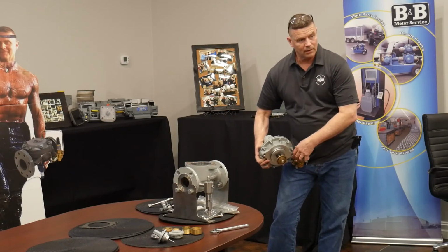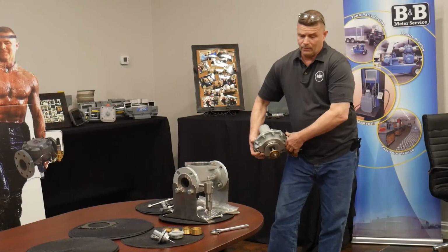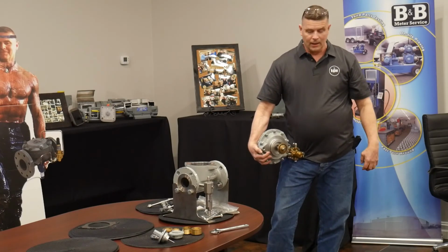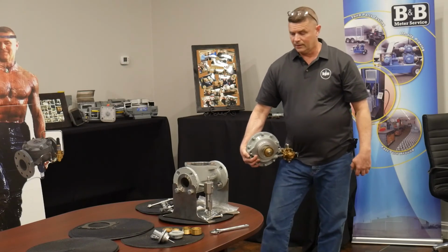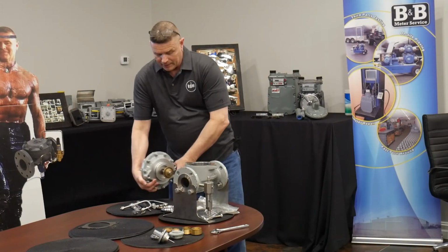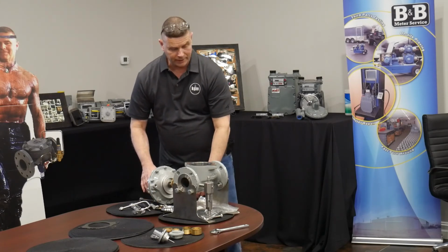What is the turn down compared to the LFRX? Okay, well the LFRX gives you 1% control, so 100 to 1. This is running probably somewhere in the vicinity of 20 to 25. If you put any of the other plug retainers in, it goes up to like 33, 35, somewhere in that range.